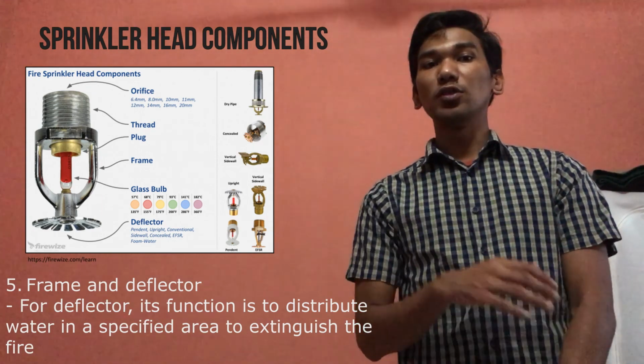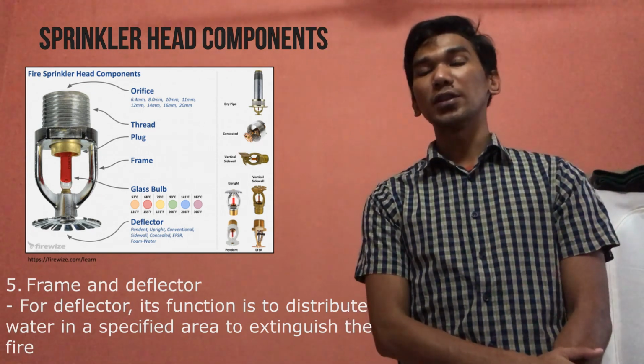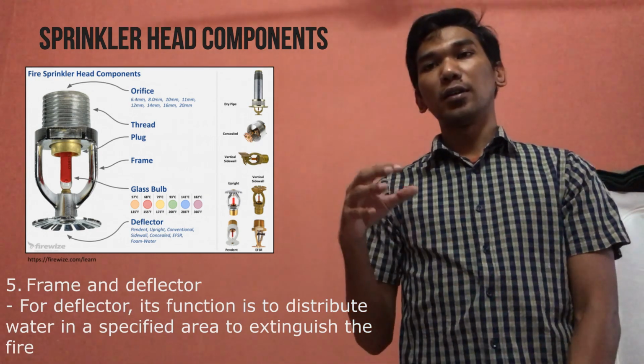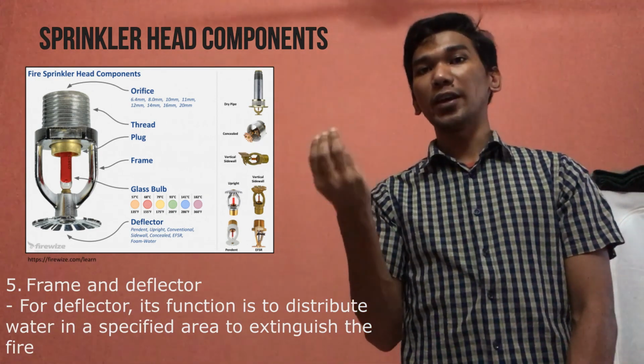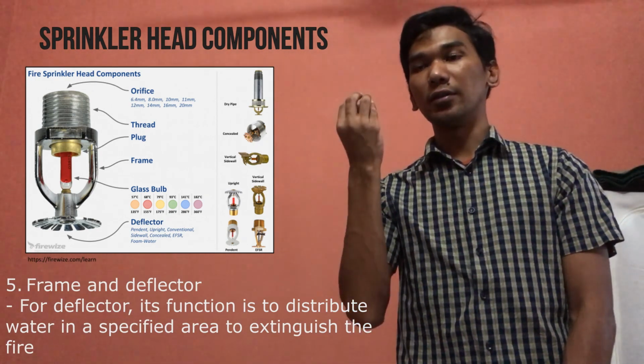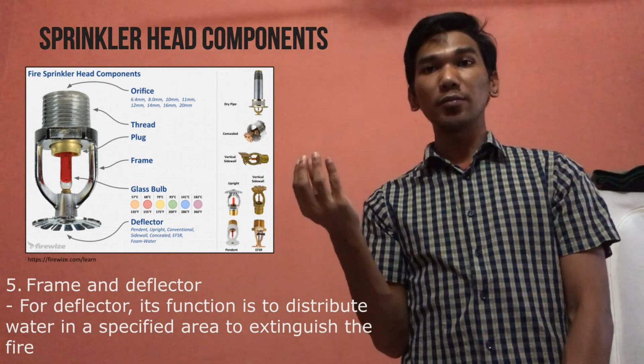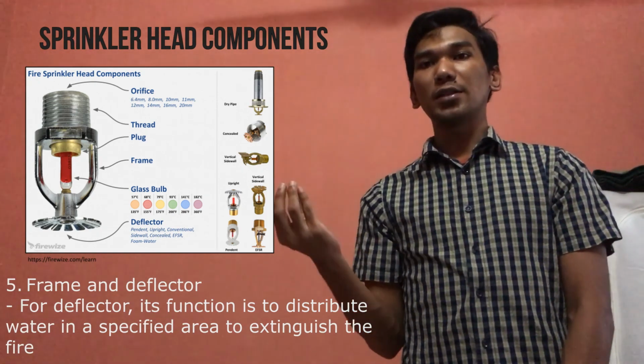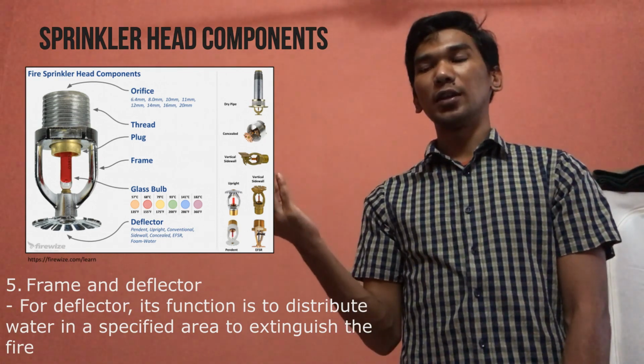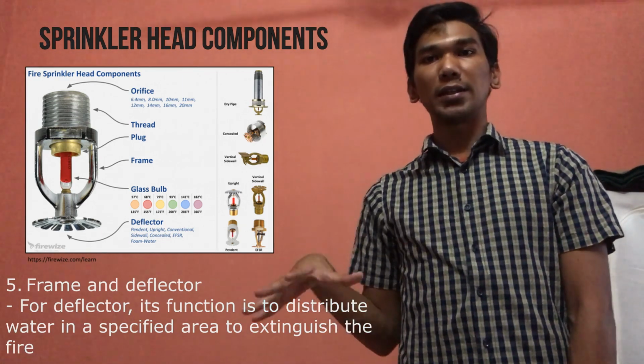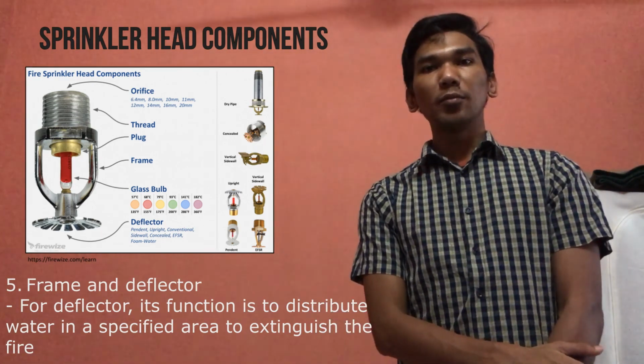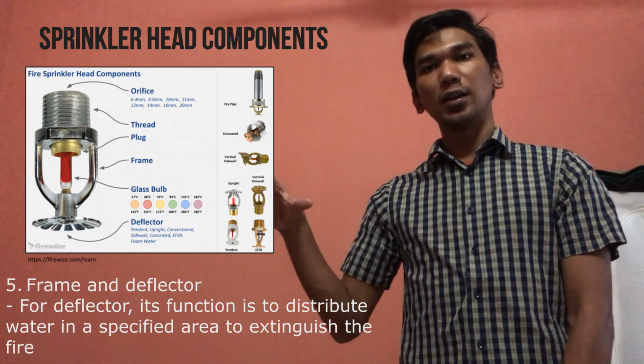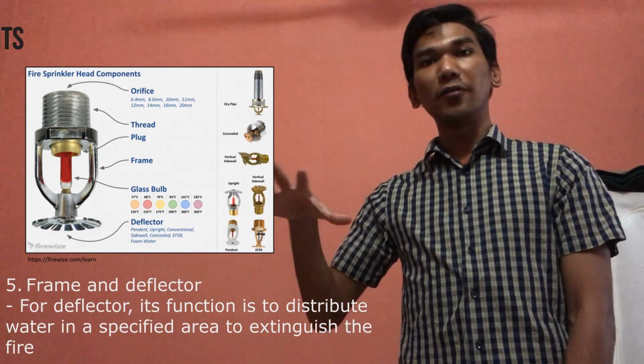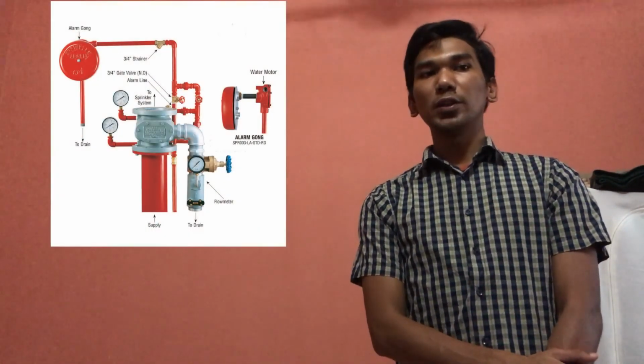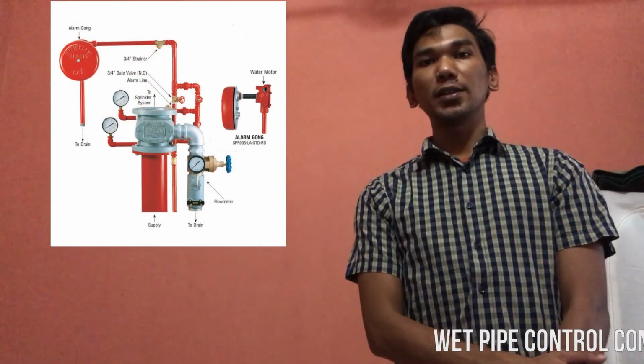So the sprinkler distributes water in a way that suits the surrounding areas. So the choosing of the deflector is very important because it depends on what type of conditions are in the building itself, because they want to spread the water evenly. And then the second one, we go to the wet pipe control components.